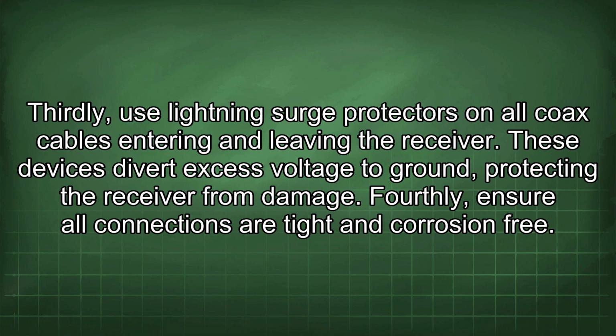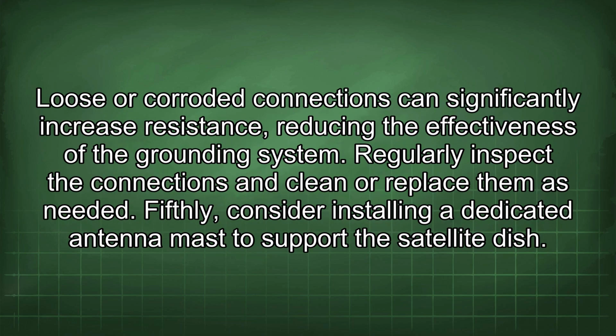Thirdly, use lightning surge protectors on all coax cables entering and leaving the receiver. These devices divert excess voltage to ground, protecting the receiver from damage. Fourthly, ensure all connections are tight and corrosion-free. Loose or corroded connections can significantly increase resistance, reducing the effectiveness of the grounding system. Regularly inspect the connections and clean or replace them as needed.